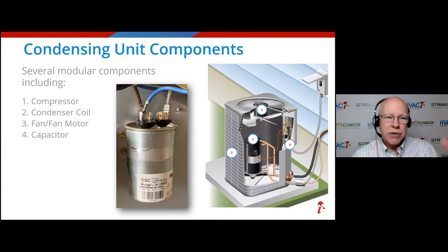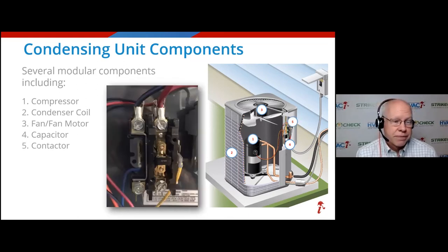But guess what? There was a thunderstorm this week, so now they're calling it lightning damage. So you do need to have everything evaluated to make sure you know what the actual scenario is and why the system's not running. The contactor is another electrical piece of equipment in the electrical compartment, and it is the electrical crossroads of this entire system. Lots of wires. Those two red and black ones coming in the top are probably 120 volts each. Very dangerous. Don't be sticking your hand in there. 240 volts.